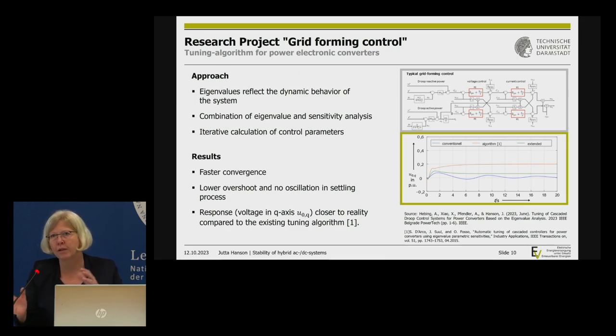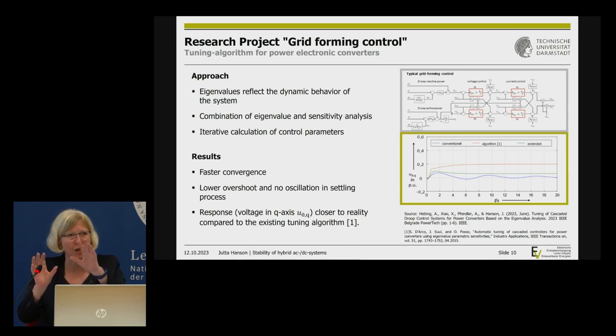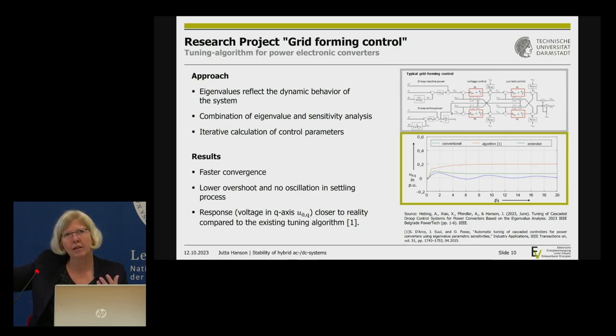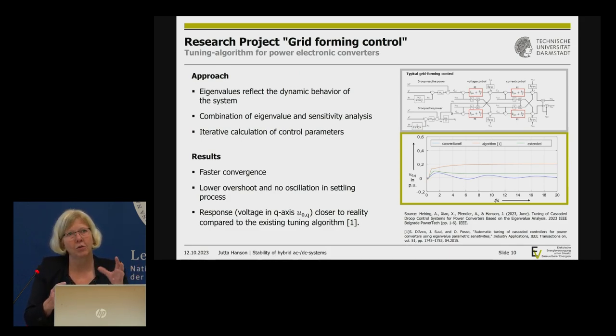Consider parameter tuning: with 20 converters and 20 controls, each with 15 parameters, how do you find all of them? We found a method in the literature and improved it. The original result oscillates in blue; a literature solution gives the red line — not oscillating but far from optimal. Our improved tuning using the system modes and eigenvalues gives the green line: not oscillating and much closer to optimal.